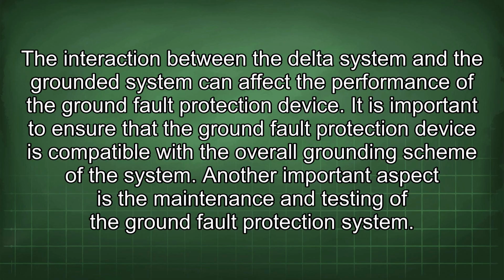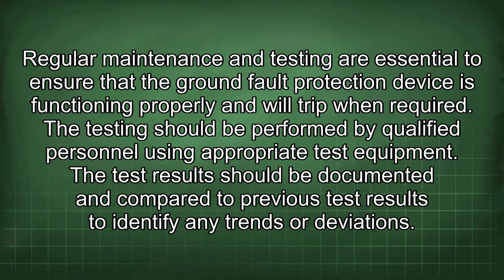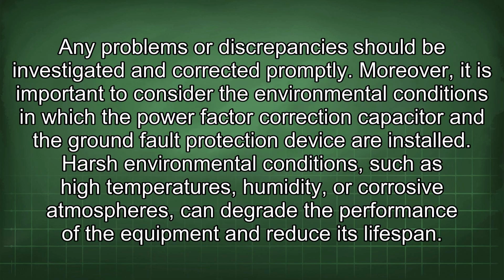system. Another important aspect is the maintenance and testing of the ground fault protection system. Regular maintenance and testing are essential to ensure that the ground fault protection device is functioning properly and will trip when required. The testing should be performed by qualified personnel using appropriate test equipment. The test results should be documented and compared to previous test results to identify any trends or deviations. Any problems or discrepancies should be investigated and corrected promptly.